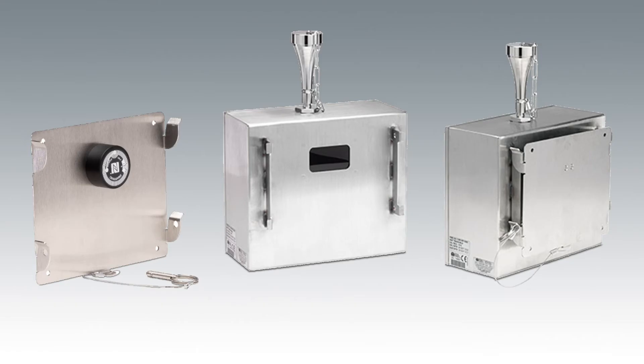Also built into that bracket, we installed what we call a smart bracket, which is an NFC tag. The NFC tag contains the basic information about that location. Previously when the unit had been serviced, it would be shipped to the manufacturer, calibrated, returned, and then the customer would have to hook a computer to it and reconfigure the IP address and put all the location-specific information back in before they could begin using it again. With the NFC mounting bracket now in place, the customer doesn't need to reprogram the system when it's returned. They can just take the unit, remount it on the wall, and the NFC tag on the mounting bracket reads the IP address into the instrument. All information about that mounting location and how the system is supposed to run is retained at that spot.